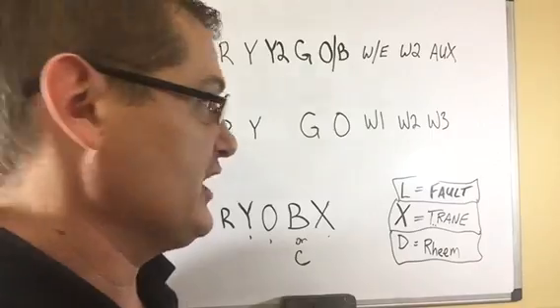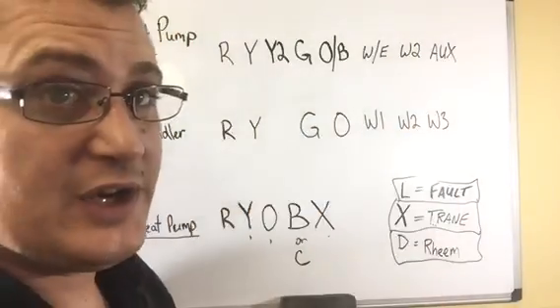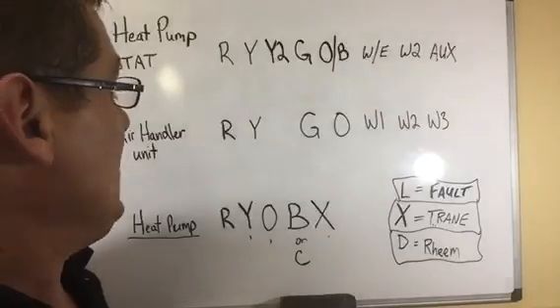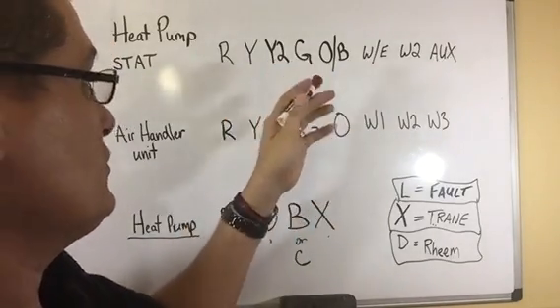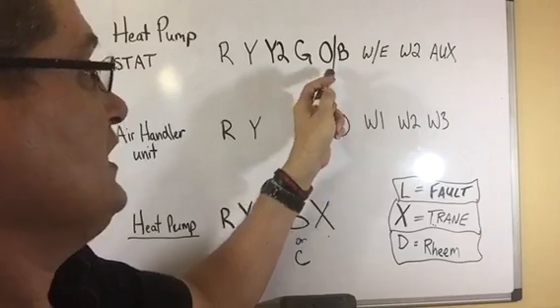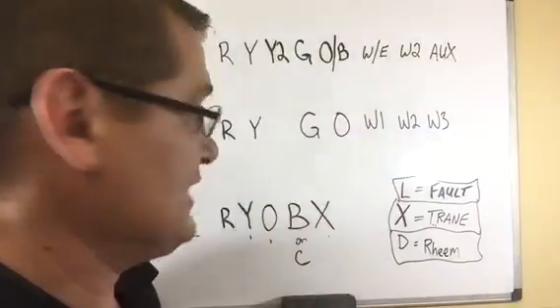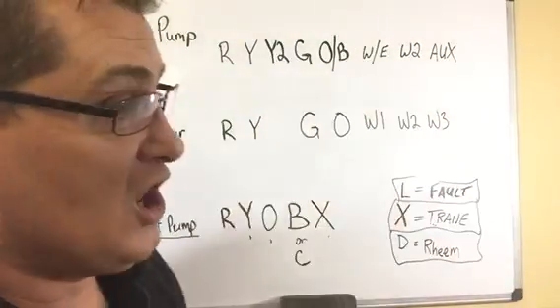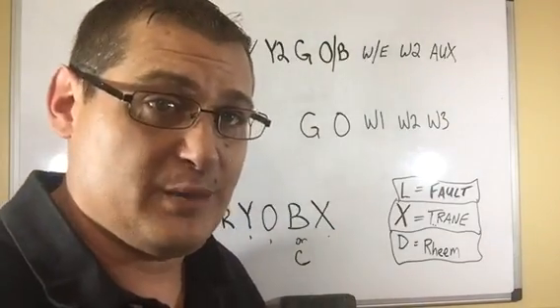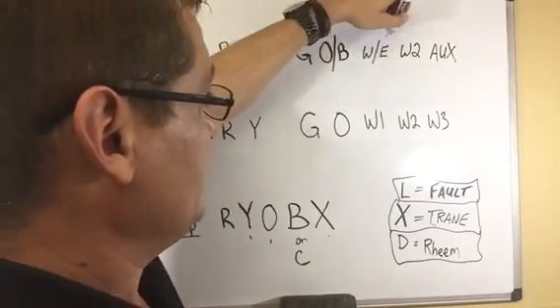Here's our typical heat pump thermostat that we had earlier. We've got R, which is power, Y, which is compressor, Y2, which we're not going to use, G is the fan, O/B or O and B, however the stat's hooked up, is for reversing valve. W, E, W2 are auxiliary. Those are all for the backup heat when we're talking about heat pumps. Really, these could all be the same terminal. You could jumper them all together and it's probably going to work out just fine for you.